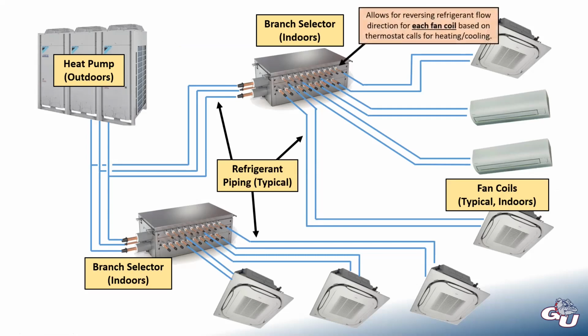That branch selector box, what this does is every pair of ports, so each one of these takes up 2 pipe connection ports on here. Inside this box is a little solenoid valve that can reverse the refrigerant flow direction based on the individual thermostat calls at each one of these units. So recall last lecture, we talked about how a heat pump will reverse the refrigerant flow depending on if it's in heating mode or cooling mode. This is effectively doing the same thing, except this is on an individual level for every fan coil. We can reverse the flow through each pair of pipes, depending on what each one of these needs.